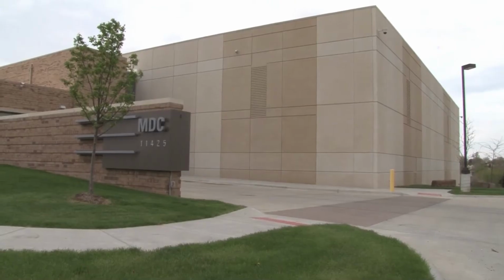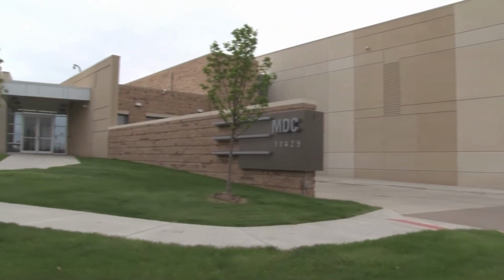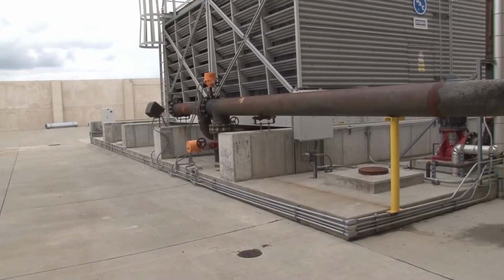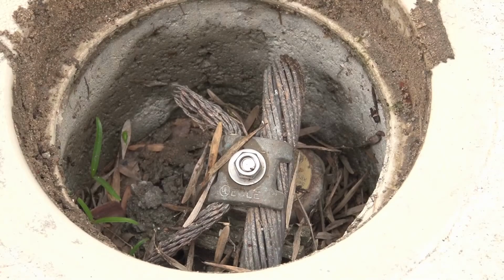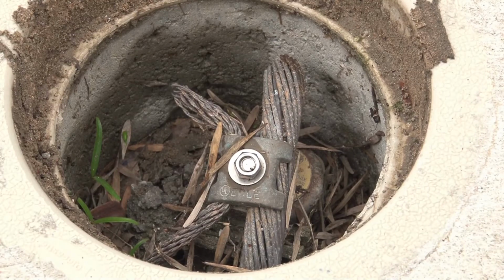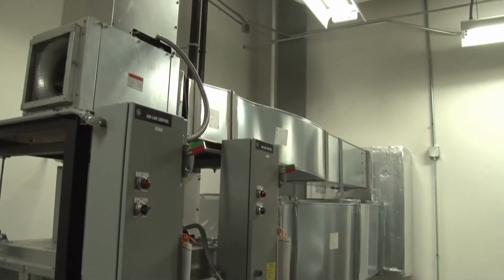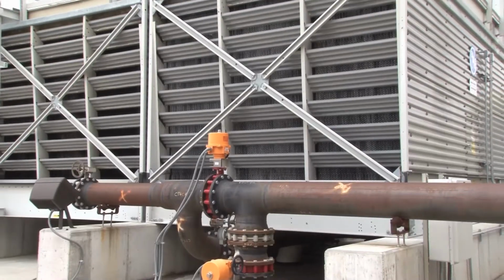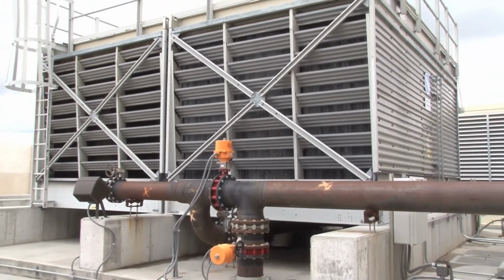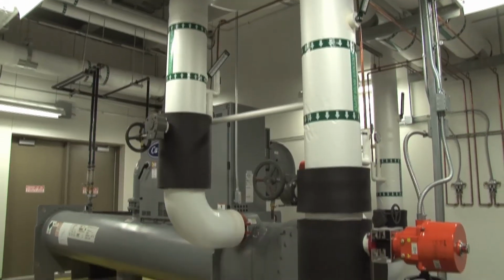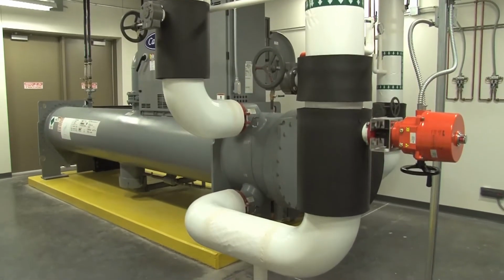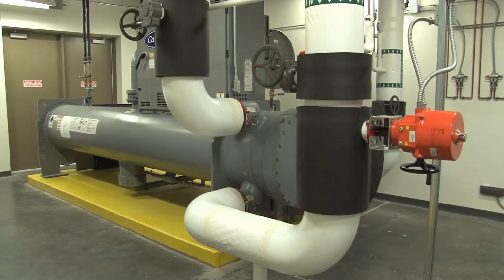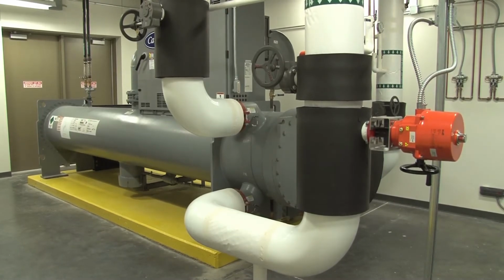Our lightning protection system consists of antennas placed on the roof. Those antennas then go into a braided copper conductor, which is extended out to our main ground electrode in the generator yard. At no time do we connect with the building steel. We have 2 Carrier chillers on site. Each chiller is a 550-ton water-based chiller. Once again, everything's redundant, so one chiller runs at a time as the other one sits idle. Each chiller has to be on its own electrical service. They cannot share any panels, so it's redundant panels feeding each device for the chillers, including pumps, water towers, fans.